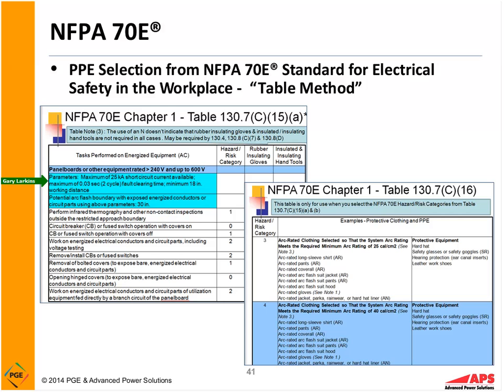They also give you working distance, which is very important because if you work closer, you can have a much higher exposure to the incident energy level. In other words, your energy level typically goes up. If you cut your working distance in half, the energy level you're exposed to typically goes up by a factor of 3 to 4 times the energy level at 18 inches. So information is available in 70E that gives you a task-based table method to pick your electrical PPE. It's a great starting point.